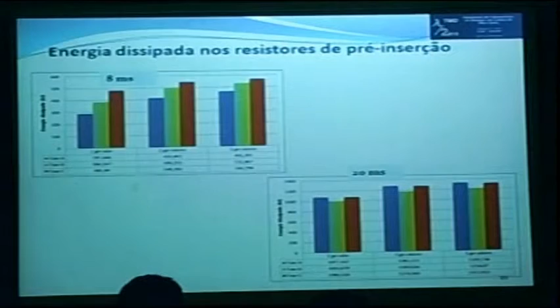This part is interesting because we are comparing a half wavelength line with a 133 kilometer line, which would be what we have extra or more than the exact half wavelength. So 180 degrees, these other 10 degrees corresponds to a 133 kilometer line. So we conducted the maneuver in the half wavelength line and on this 133 kilometer line just to see the disturbances that we would get.